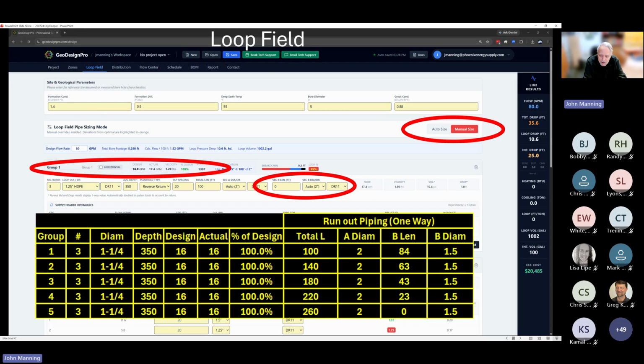So that simple task has achieved 100% balance. And I would suggest it's probably more accurate than balance valves that are typically only accurate to plus or minus 5% anyway. So this is one approach, and by doing this, we've actually saved money. We're using smaller pipe. The internal volume gets smaller, so we saved a little bit on antifreeze. So for virtually no cost, we've achieved perfect balance.